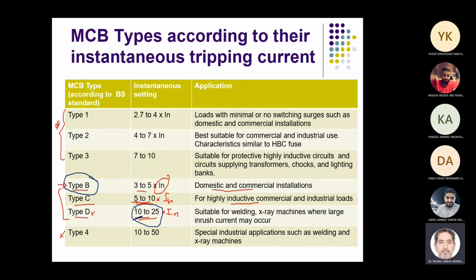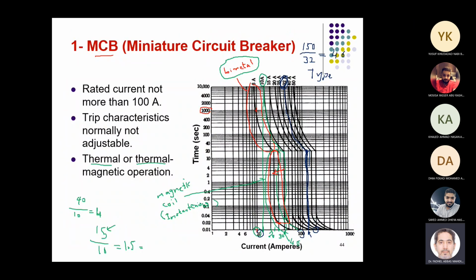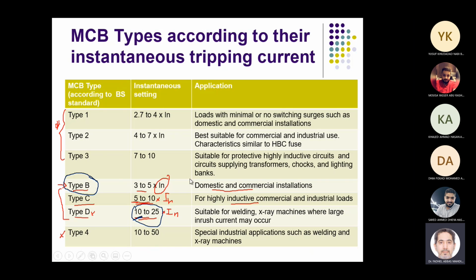This is for low voltage breakers. Also, the MCBs are classified according to the instantaneous elements. So type B, C, D. I don't go over these details because this is not the subject of today, which is high voltage breakers. So type B, for example, are low voltage MCB breakers that operate their instantaneous element, which is the magnetic coil, at 3 to 5 times the rated current. Type C, 5 to 10 times. Type D, from 10 to 25 times the rated current.